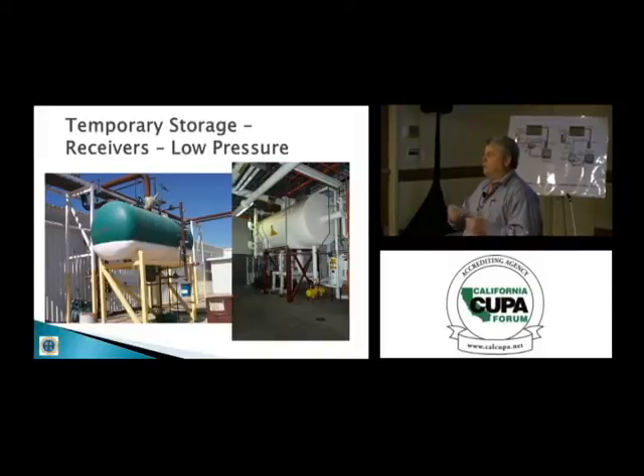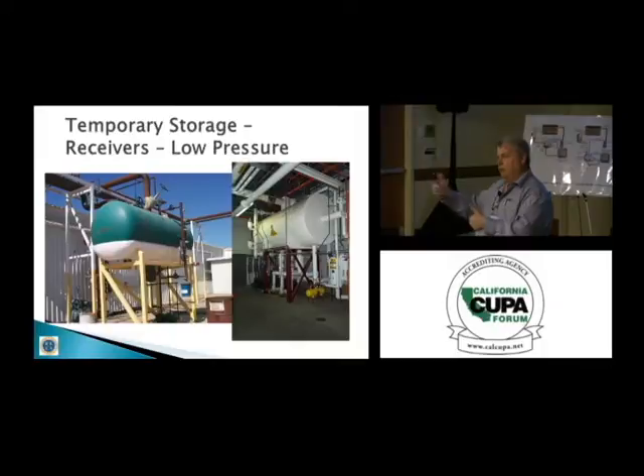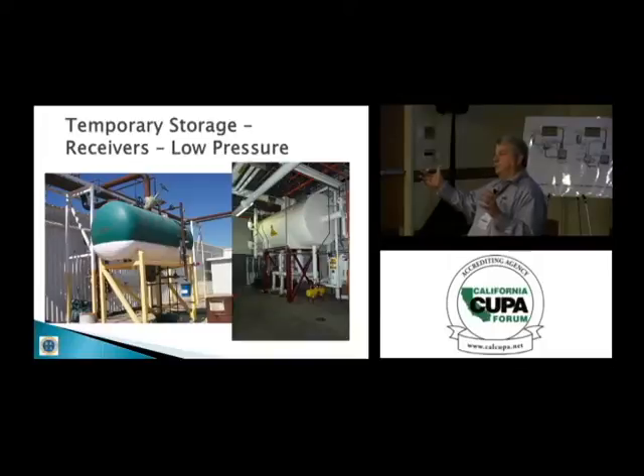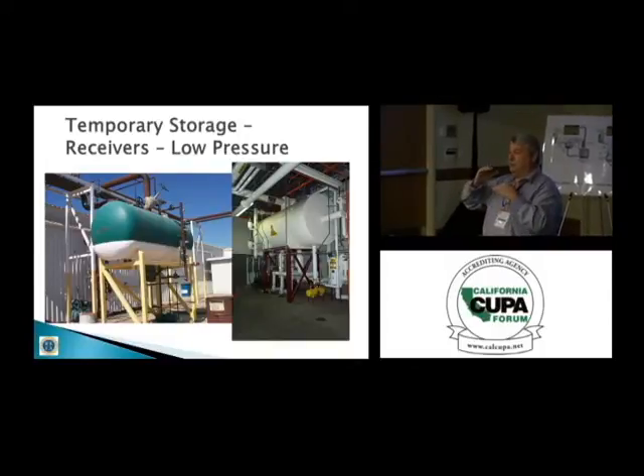Yes, thank you. And that's why I hesitate to put a number on it. Some processing plants will actually transport some of their equipment to another processing plant, so they're opening and closing, and it's a more difficult job tracking your inventory level. That's why the vessels are sometimes sized the way they are, because if you take away part of the process to be used in another location, you don't take the refrigerant with it, you leave it in your system. So wintertime levels might run a little higher in a vessel compared to summertime because of where you're using it.